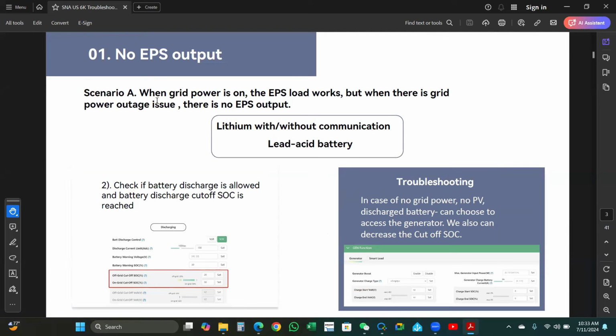Step 2. Scenario A, when the grid power is on, the EPS load works, but when there is a grid power outage issue, there is no EPS output. This is lithium with and without communication, lead acid battery. Second, check if the battery discharge is allowed and the battery discharge cutoff is reached. This is for the SOC, and the bottom one is for the voltage for lead acid mode. Troubleshooting: in case of no grid power and no PV, discharged battery, you can choose to access the generator. We also can decrease the cutoff SOC.